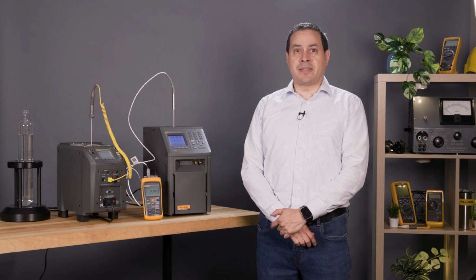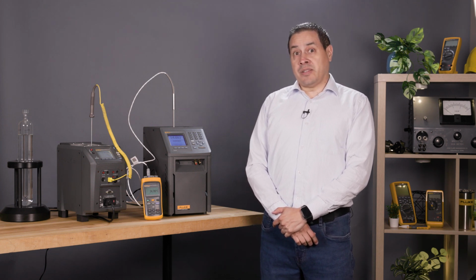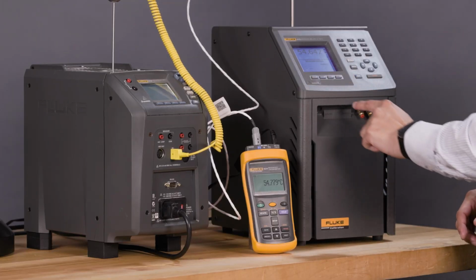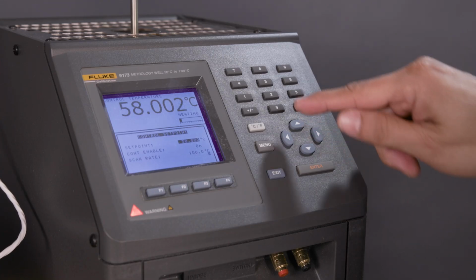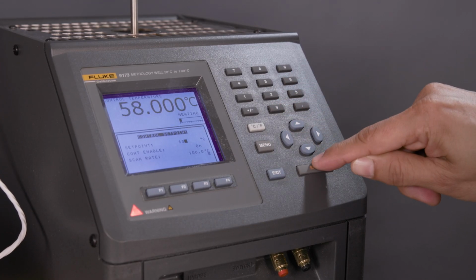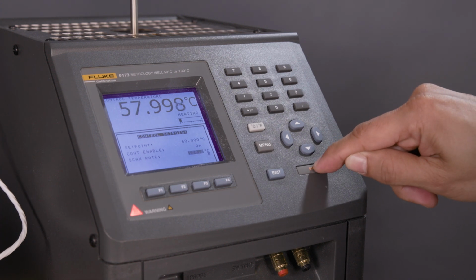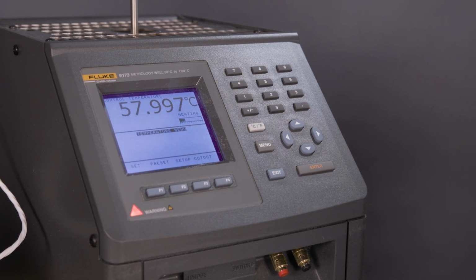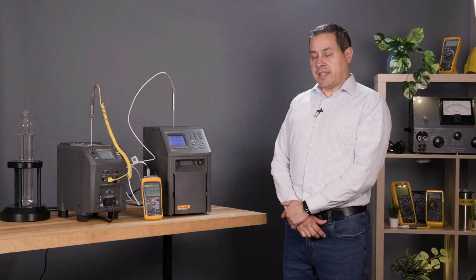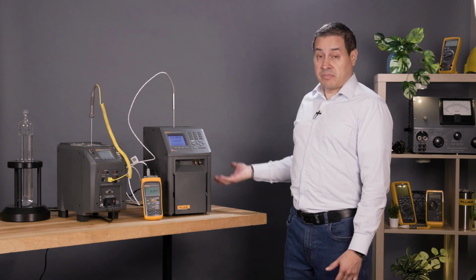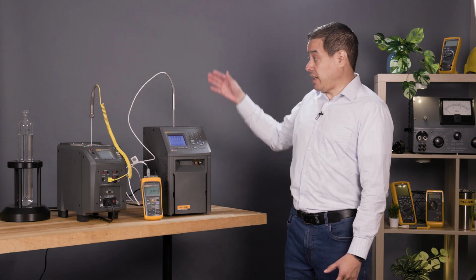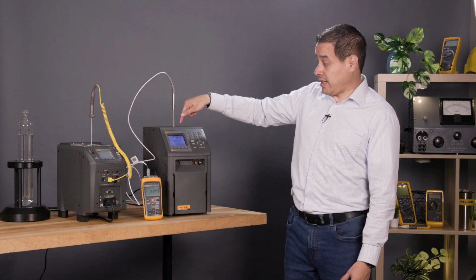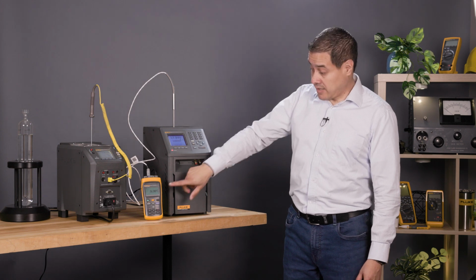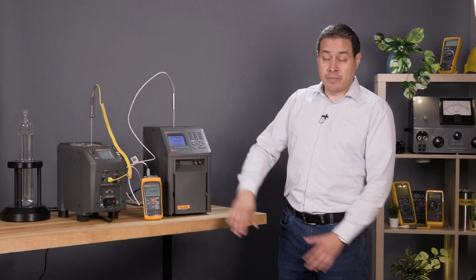So once you've selected the test points or the set points, let's input one of those in the dry well. In this case, 60 C. And it will go to 60 C. While we wait, the calibrator gets to 60. What is happening inside is it's heating the internals, heating the probe. So you can see this is getting to 60, and this is a little bit slower, it's common.